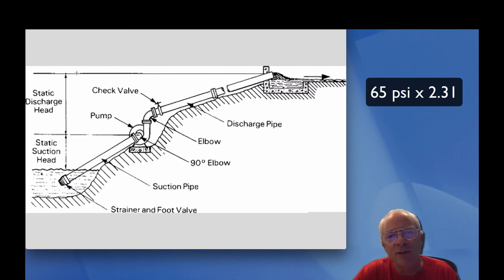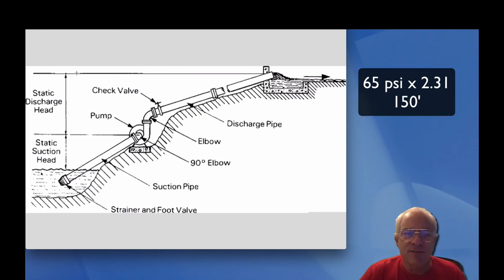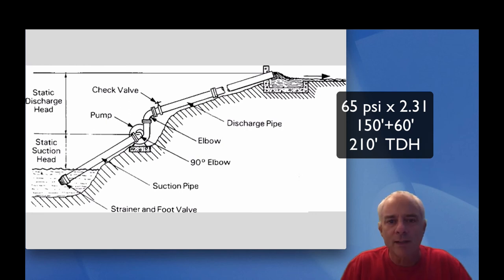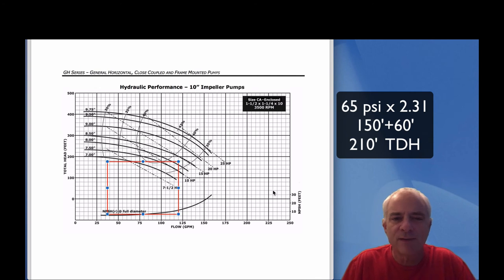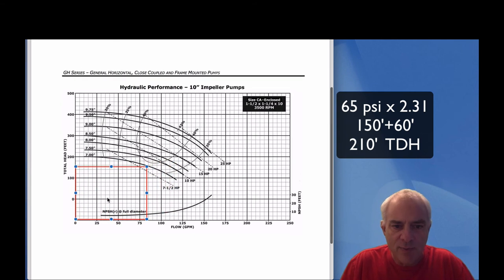65 psi - the way you convert it is multiplying by 2.31. You should get that number in your head: 2.31. You take 65 times 2.31 and that is 150. So 150 more feet of head we have to add to our total dynamic head to pressurize those sprinklers properly. We were at 60, so now we're going to be at 210. Now we would go to a curve that would fit our duty point better.